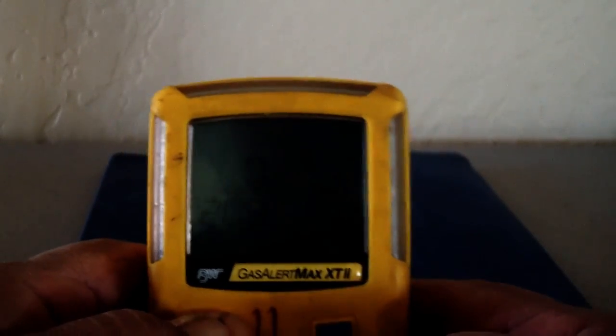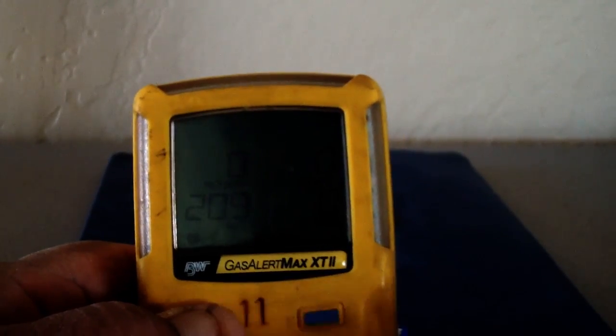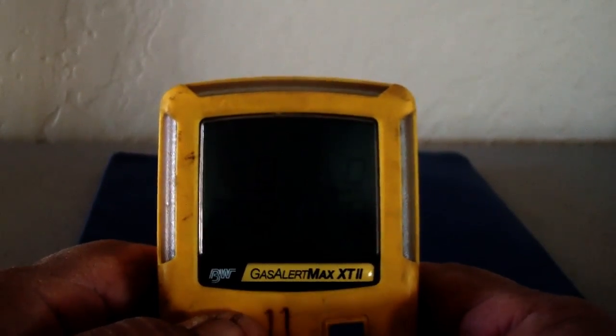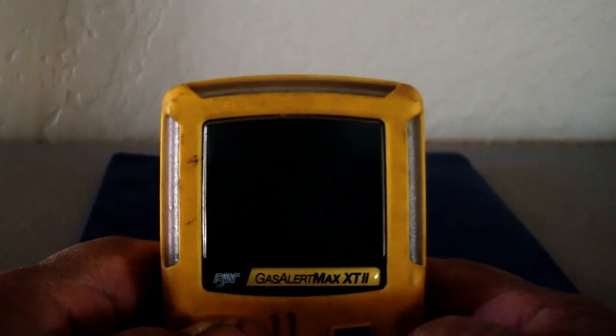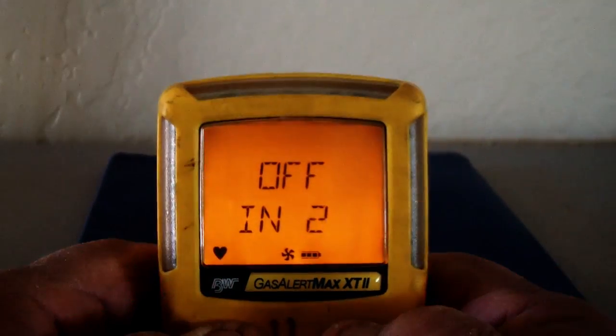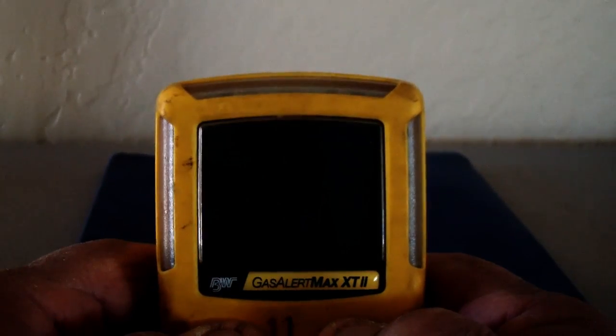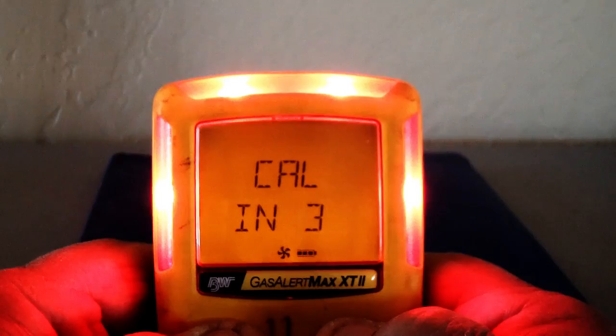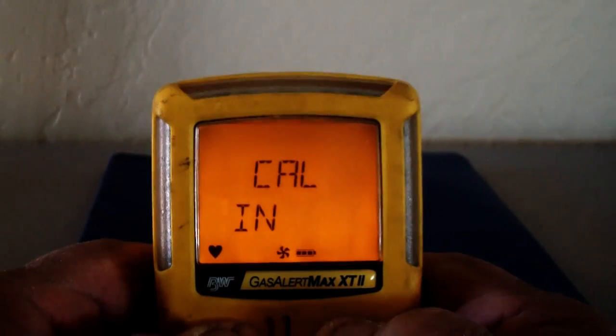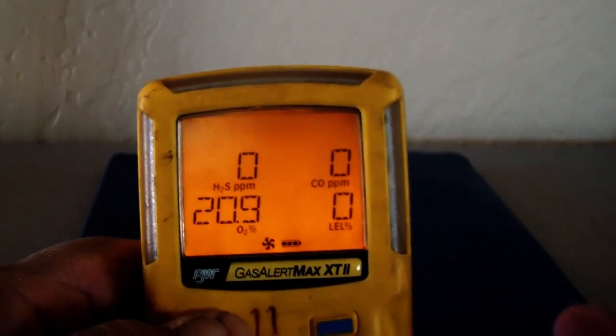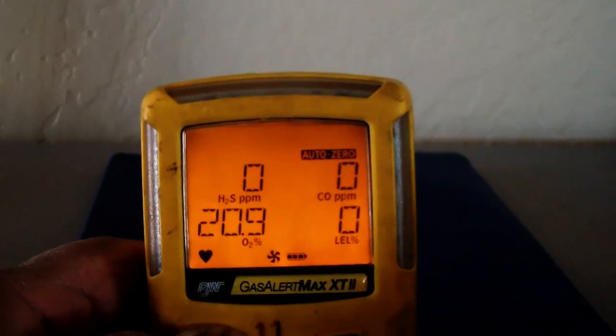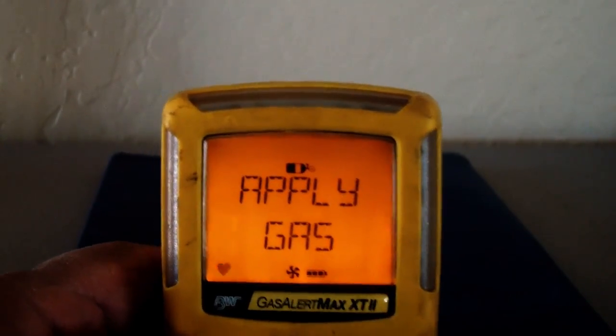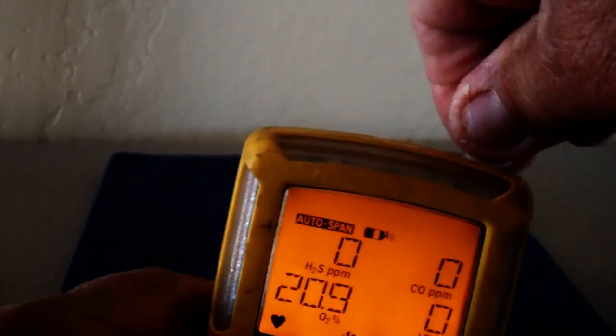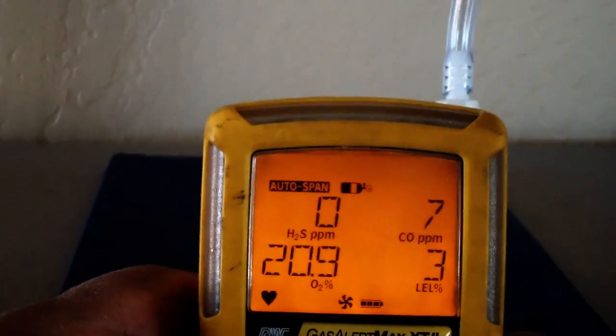Remember, one button operation. You're going to use that on-off button, and you're going to push and hold that button and look at the screen and do what the screen tells you. So when I push it, it's going to go into the off mode. I never let up on the button. Never let up. Now I'm going into cal mode. Once I get into calibration mode, I can let go of the button, and I wait until it tells me to apply gas. At that point, I attach my gas.